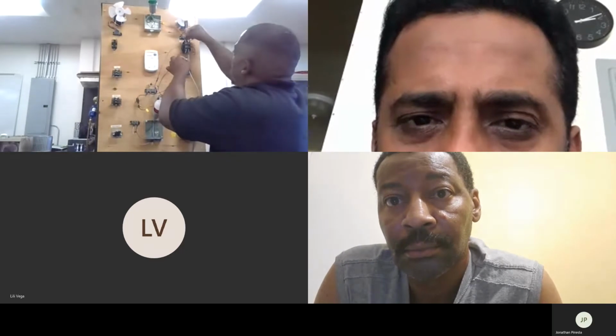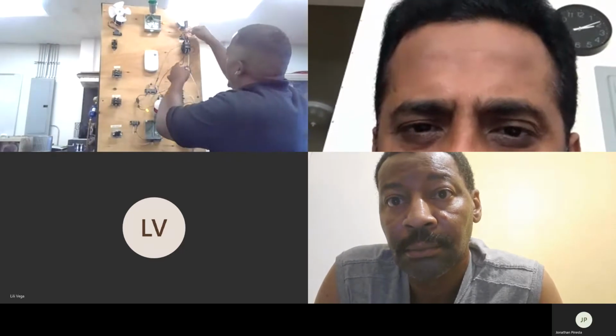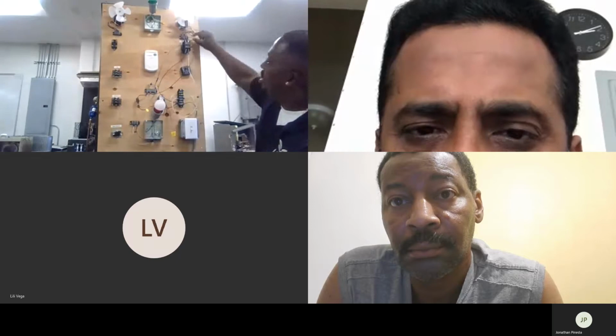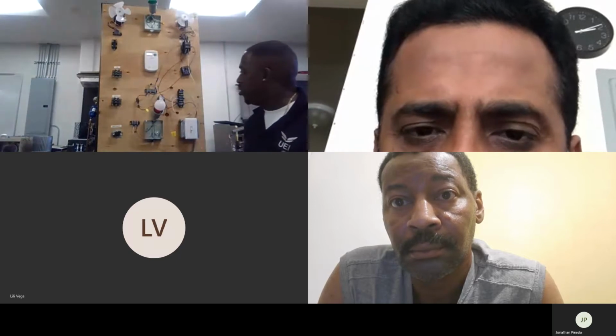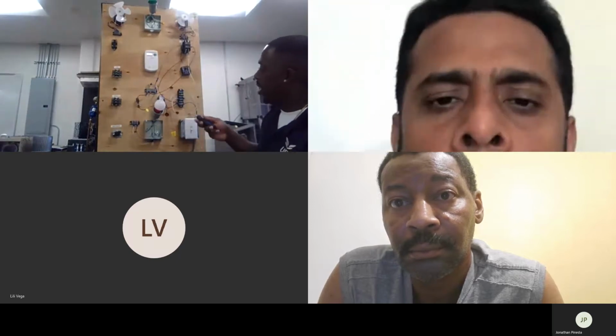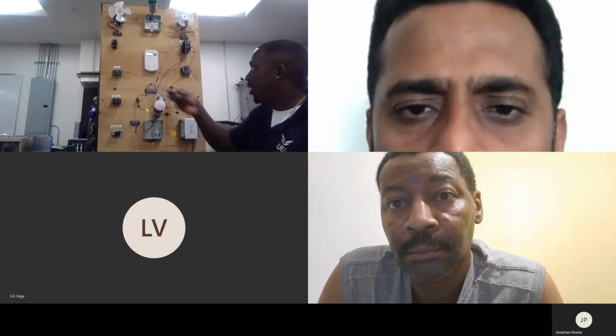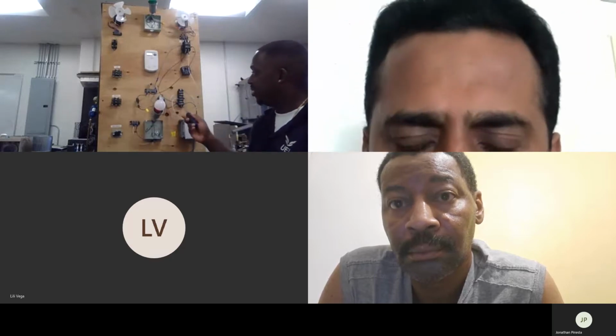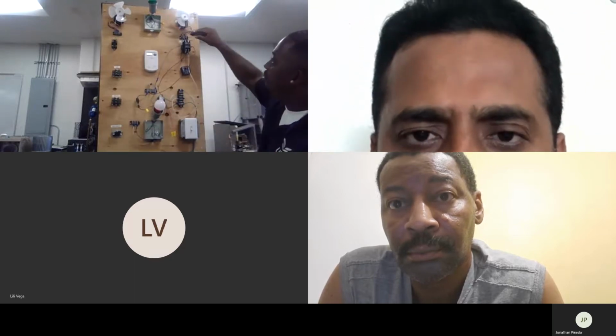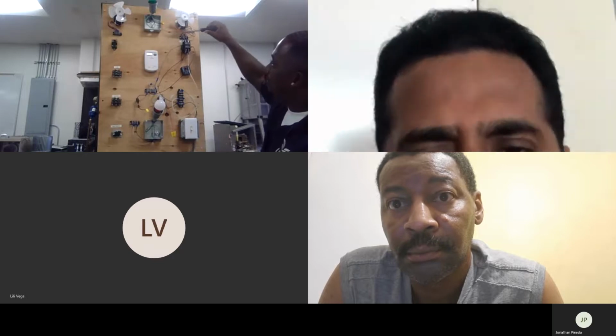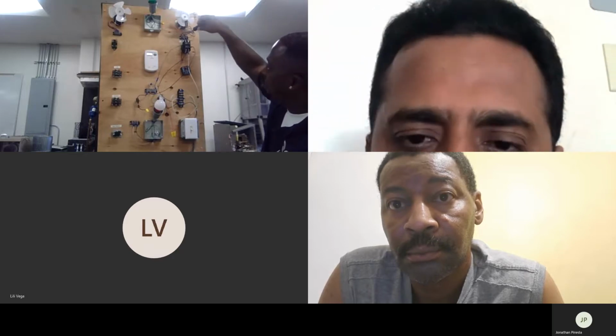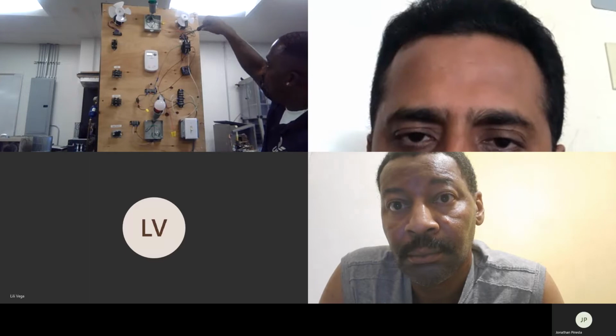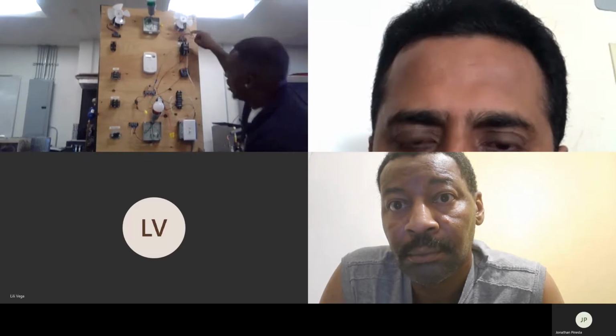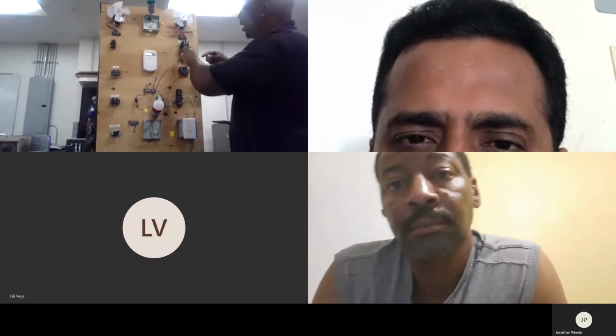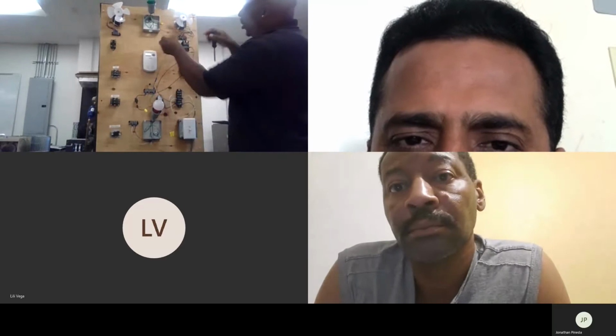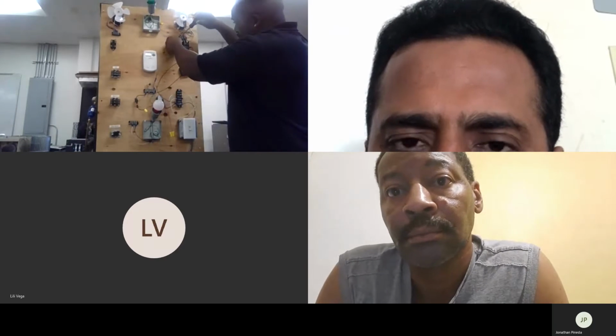So I'm going to connect one here. I know it must be kind of hard to see, but just like I was talking about on this little terminal strip, I got L1 connected here, so any of my other L1s need to be connected in that same bay. The same thing's happening up here on my fan - I got 2 wires connected on this first screw and then on this third screw. So when I connect from my contactor to the fan, I want to make sure I put my first one on that first screw.